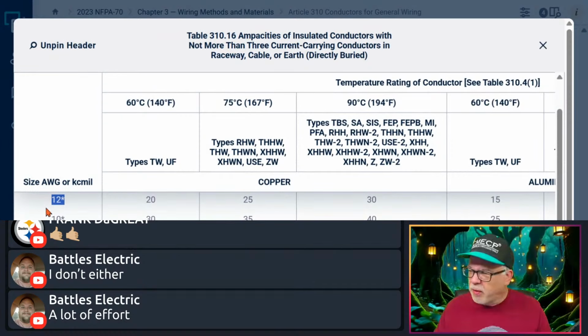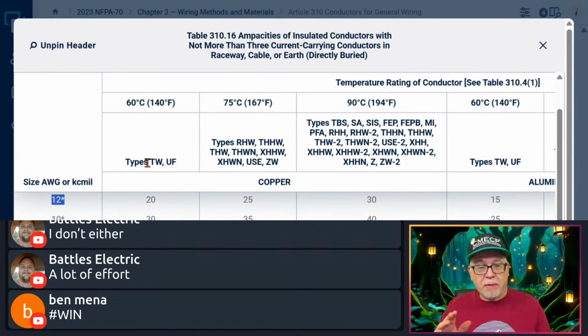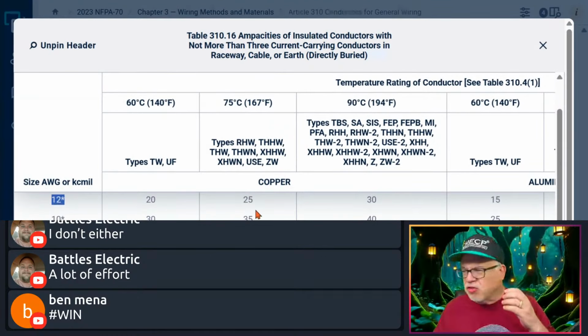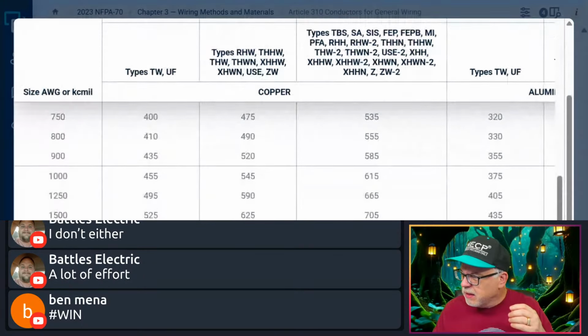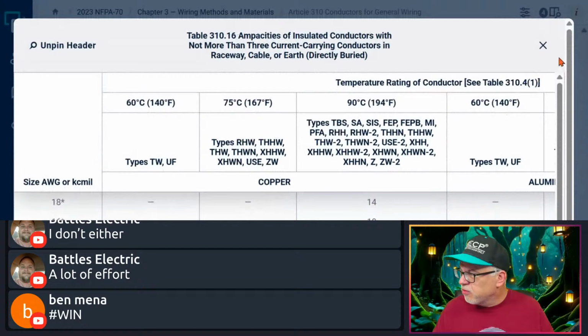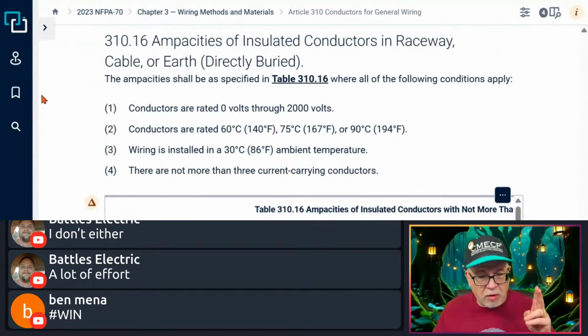Okay, so you're saying, well, Paul, don't I have to use the 60? No, because I told you the lugs were 75. The wire is rated at least 75. Now you're saying, yeah, but Paul, what about those small conductor rules? Because you see this little asterisk right here? It says, wait a minute, you have to go down here and look at 240.4(D). All right, I got you. So we're going to go look. We think we're going to be 12 because it's 25 amps under the 75 degree.